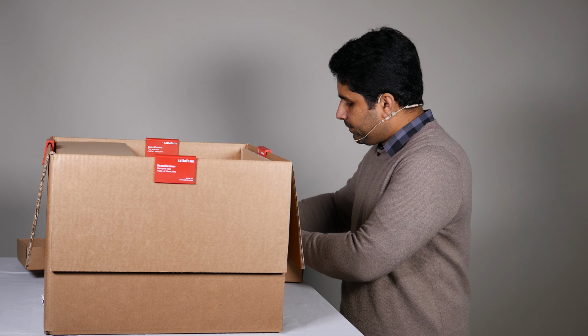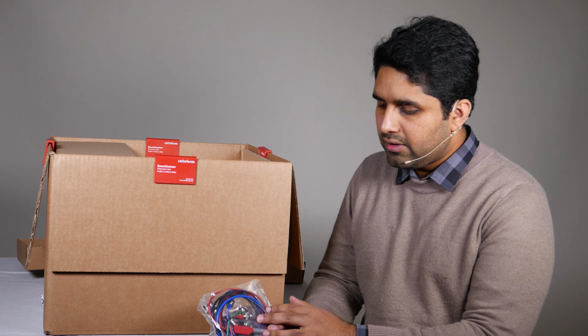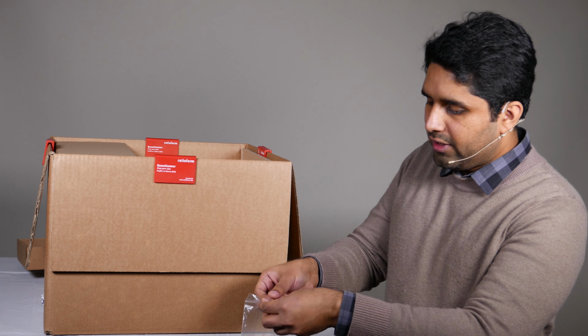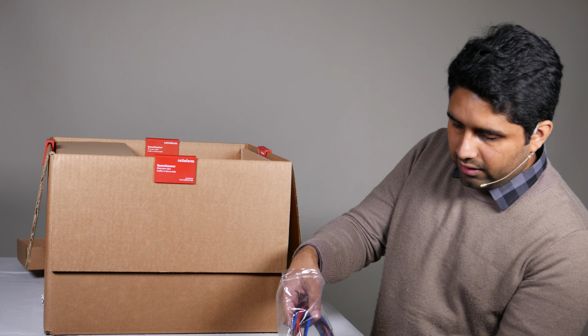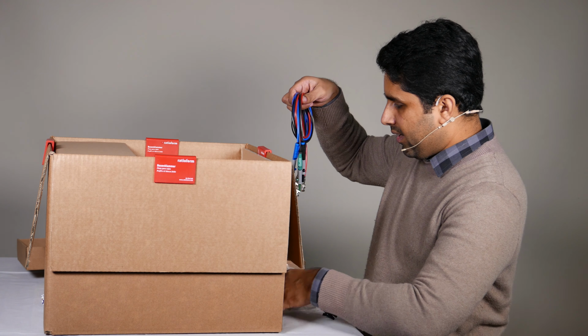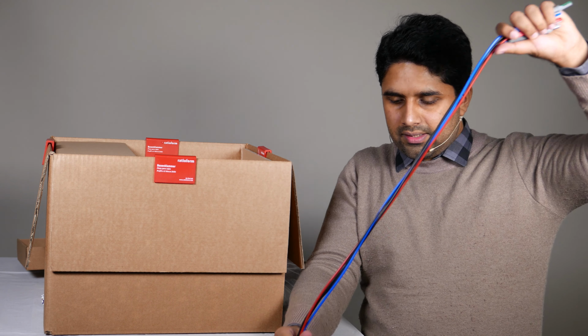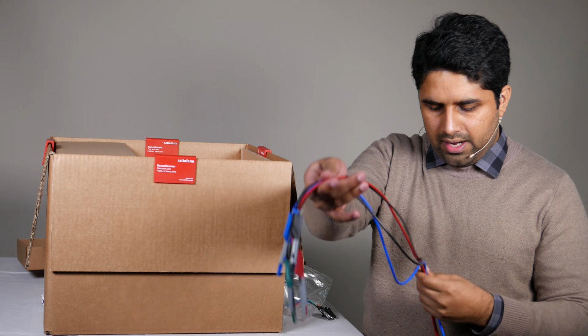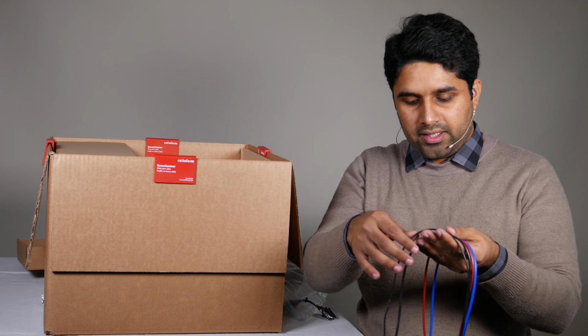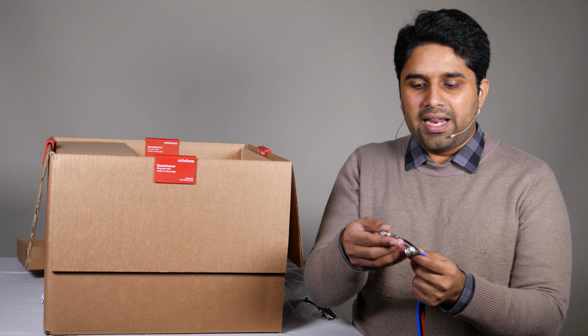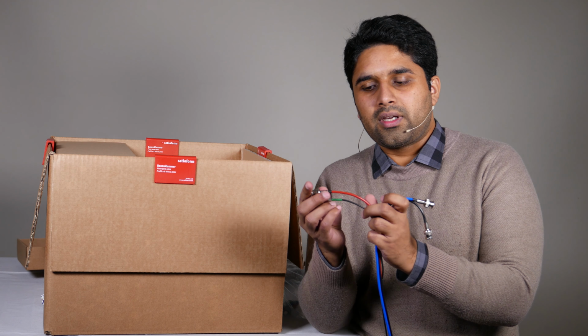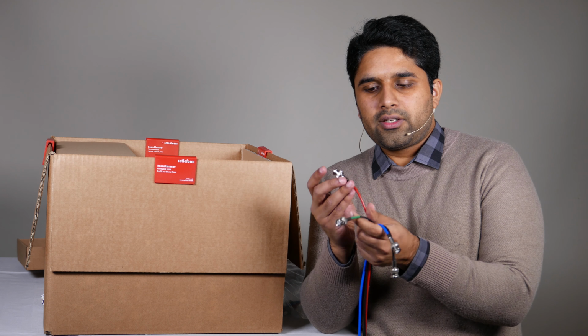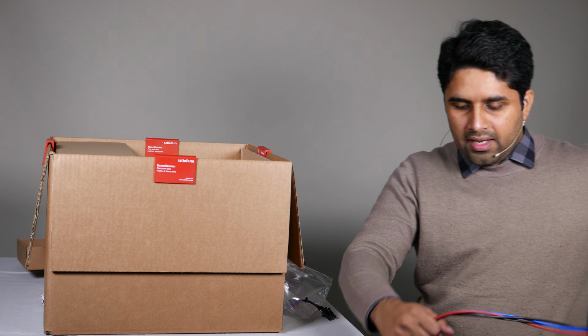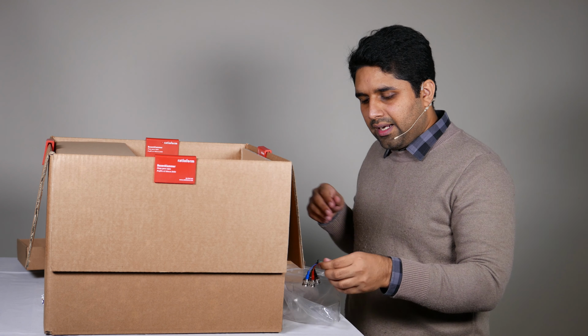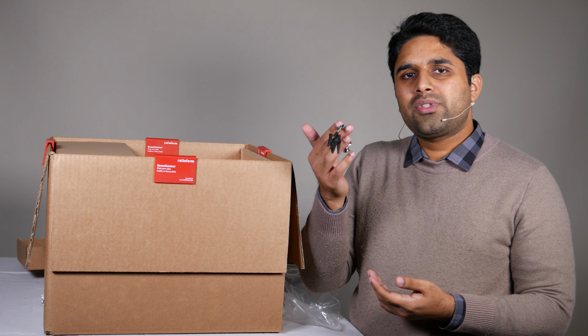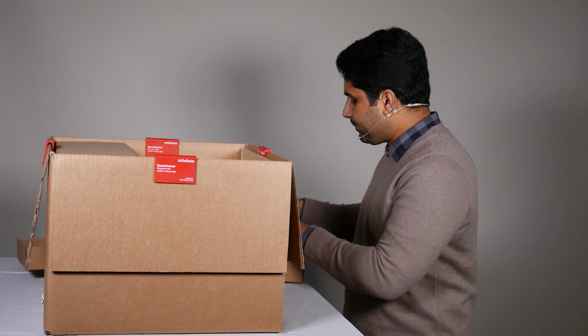At the end we have two sets of cell cables. One is these long cell cables, which are 1 meter long. So let me take them out for you. These are 1 meter long cell cables, as you can see, and we have 4 different colors. The black one is for the working electrode, the blue one for the working electrode sense, the green one for the reference electrode, and the red one is for the counter electrode. And then in addition to that we have the shorter cell cables. So make sure that you have these 2 sets of cell cables with you in the accessories.